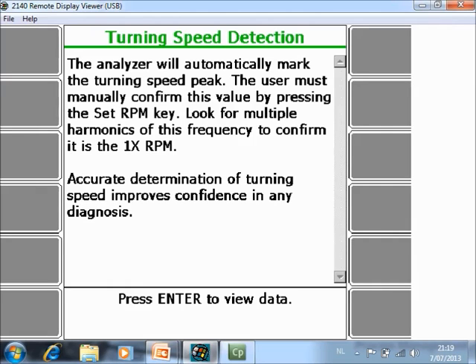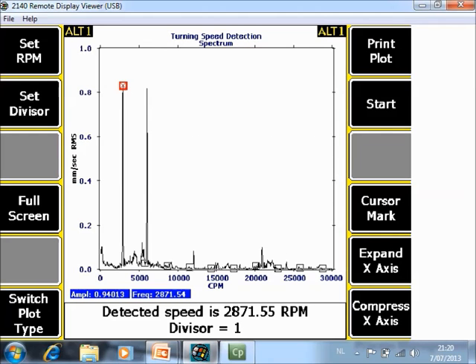Now it asks you to press Enter to view the data. Immediately it places a cursor on a peak in the neighborhood of 3000 RPM. In this case the highest peak in the neighborhood is at 2871 RPM, and it suggests that this is the turning speed of the installation. If you are convinced that this is correct, you can push F1 to store this data and then continue with normal vibration data based on this speed.